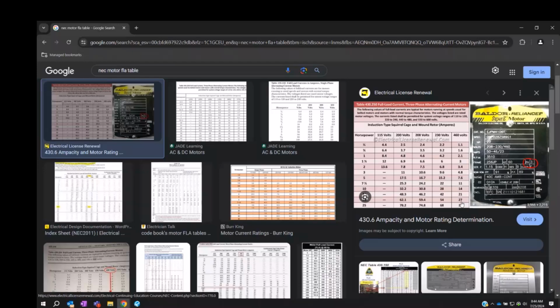So like you're saying, this horsepower, for motors specifically, is described in horsepower from a mechanical standpoint. That's what we give you. But why you need the horsepower is because it's in relation to kVA. It has nothing to do with kilowatts. Correct. That is describing the total power needed for this motor. It's not giving you the division of the reactive and the real power, correct? Correct. Okay. Like you said, you get the horsepower, you get the voltage, which gives you the amps, and then you multiply that by the equation to give you kVA.